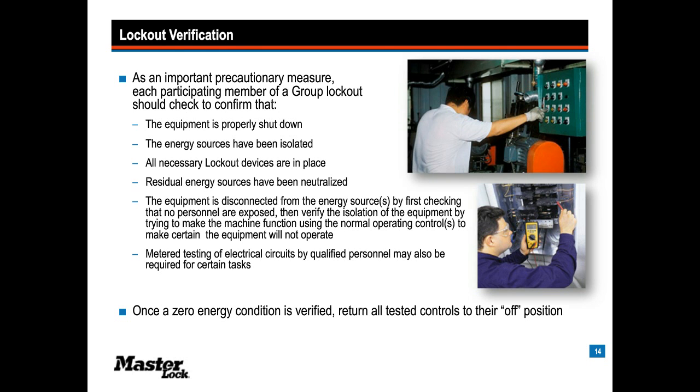Where electrical contact with live parts potentially could take place, it's important for a qualified person to go in using a meter and verify that a truly de-energized state has taken place. Okay? Once zero energy is verified, tested controls should be returned to the off position so they don't suddenly start up once the lockout has been removed and energy has been restored.